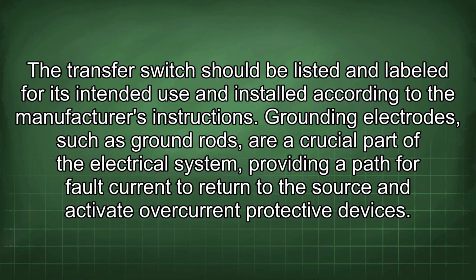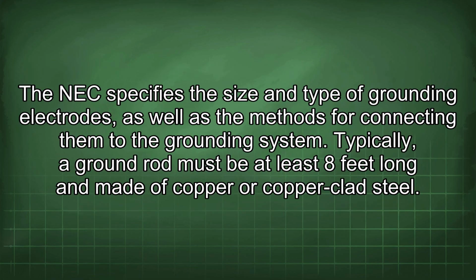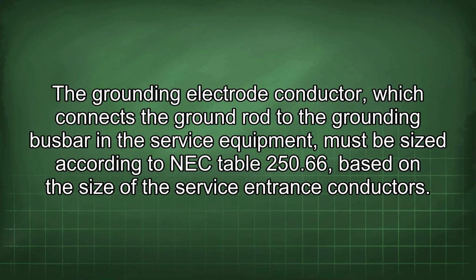Grounding electrodes, such as ground rods, are a crucial part of the electrical system, providing a path for fault current to return to the source and activate overcurrent protective devices. The NEC specifies the size and type of grounding electrodes, as well as the methods for connecting them to the grounding system. Typically, a ground rod must be at least 8 feet long and made of copper or copper-clad steel. The grounding electrode conductor, which connects the ground rod to the grounding busbar in the service equipment, must be sized according to NEC Table 250.66, based on the size of the service entrance conductors.